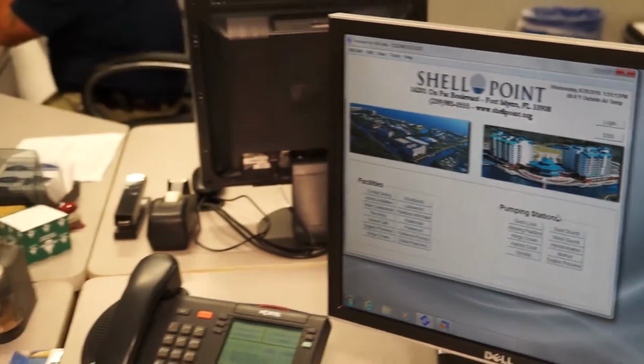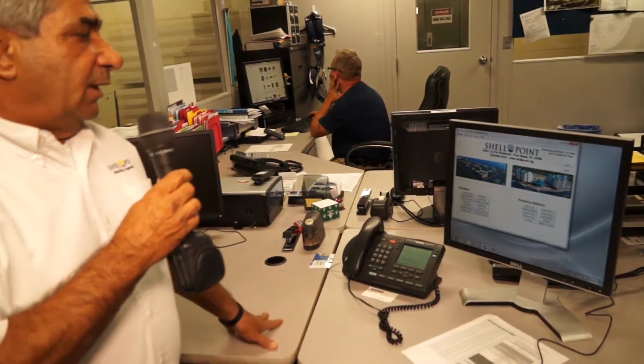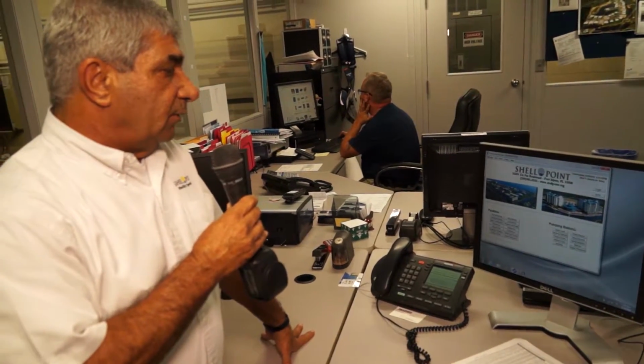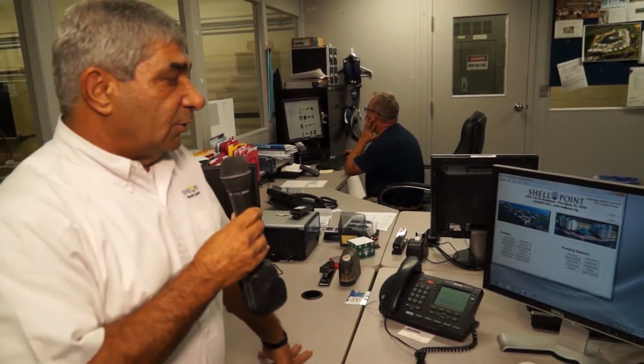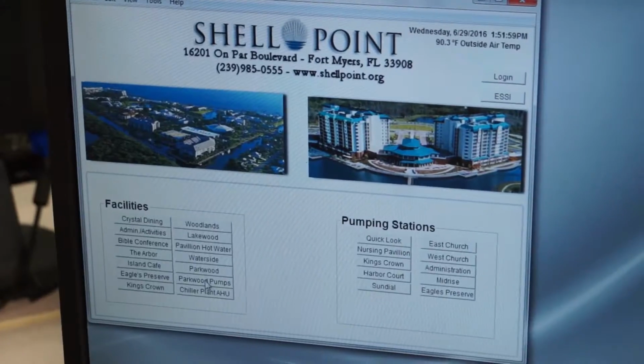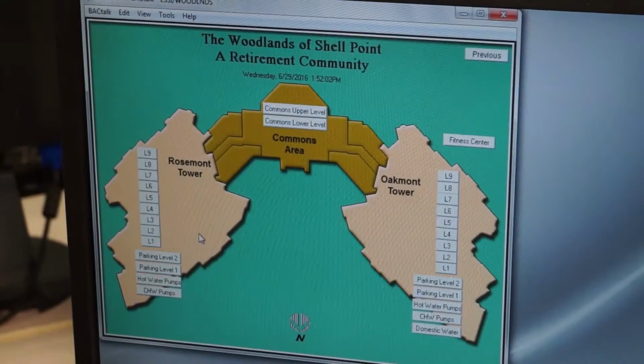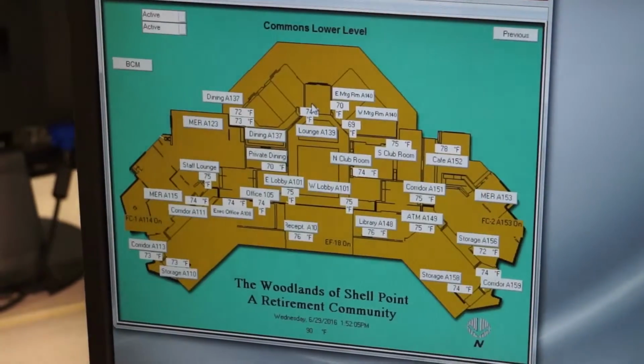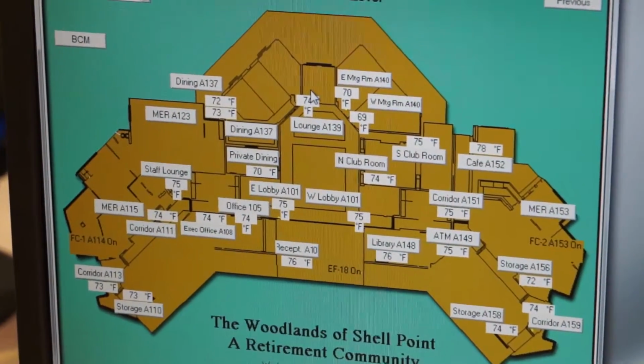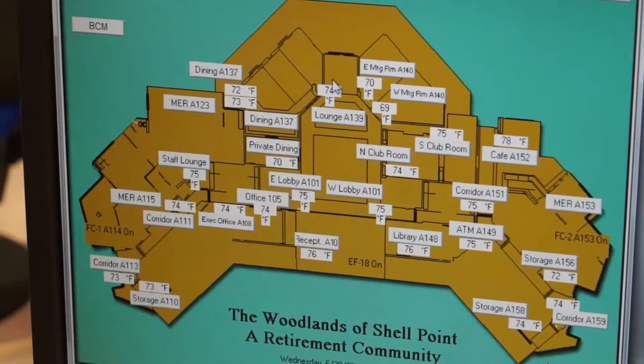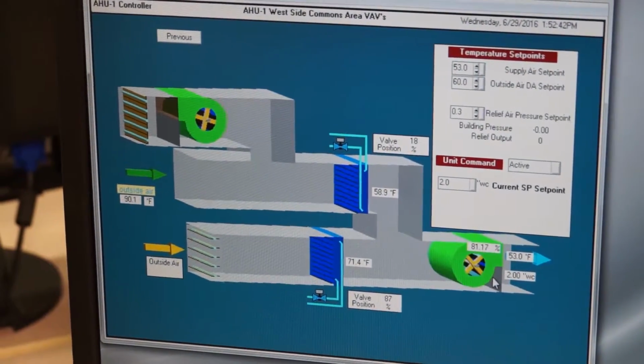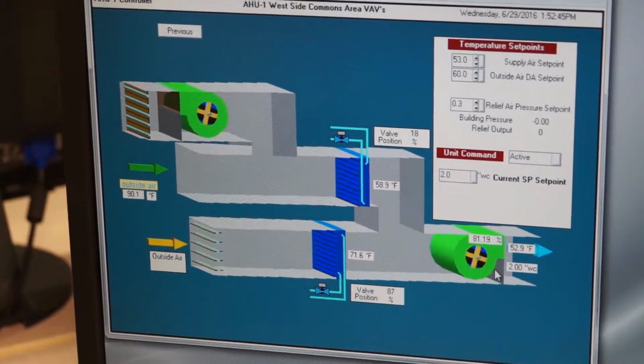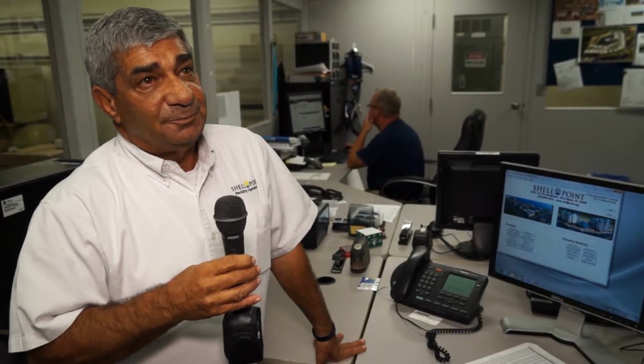This system goes out through all the property, so we can monitor all the buildings on the island, the woodlands, and Eagle Preserve. The only thing we do not monitor here is individual units. So at any given point, if somebody complains in a common area, church, pharmacy, or any building like that, we can look and determine if we need to send somebody. We can also make adjustments to pumps, thermostats, controls, and systems right from here without having to leave unless absolutely necessary.